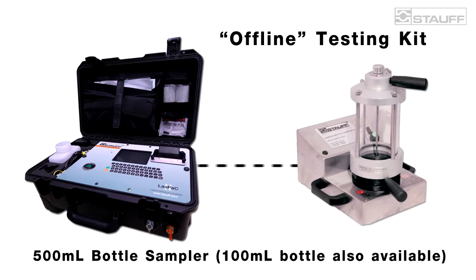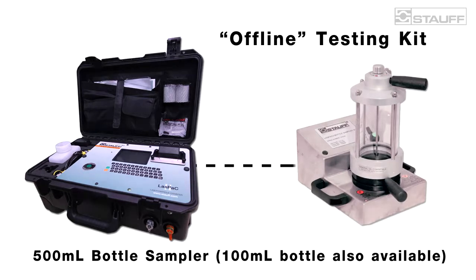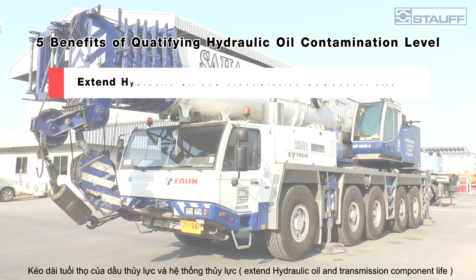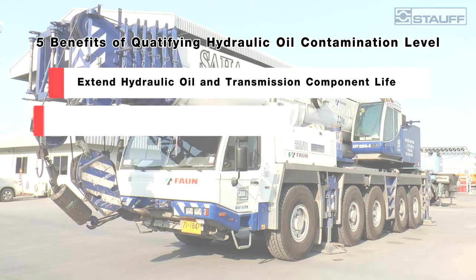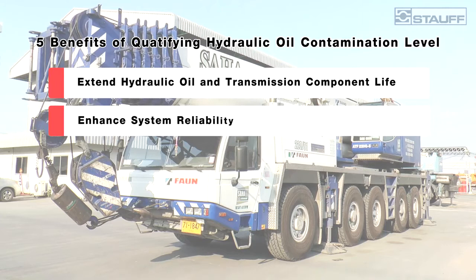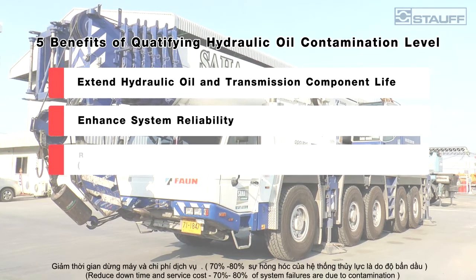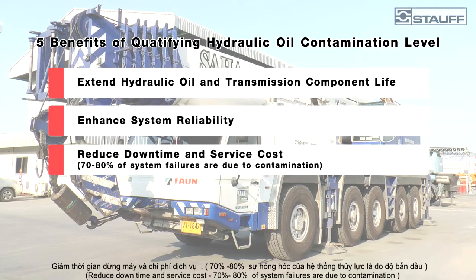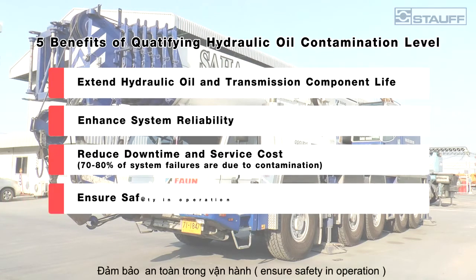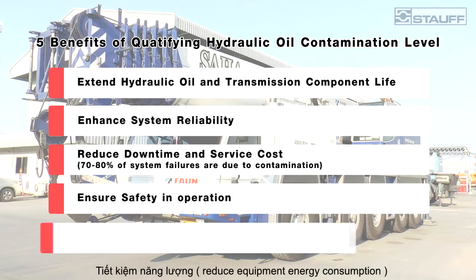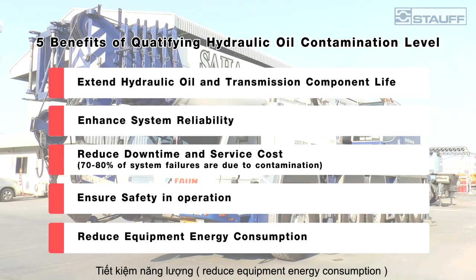Five benefits of measuring and quantifying the numbers of solid contamination in hydraulic oil: extend hydraulic oil and transmission component life, enhance system reliability, reduce downtime and service cost. Note that 70 to 80% of system failures are due to contamination. Additional benefits include ensuring safety in operation and reducing equipment energy consumption.